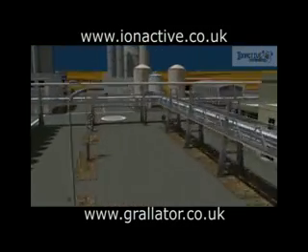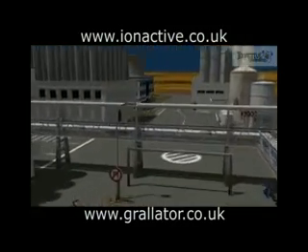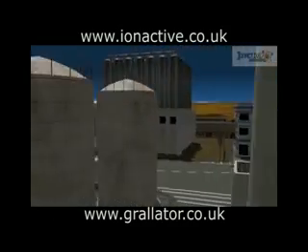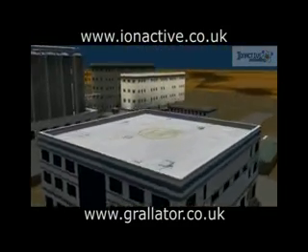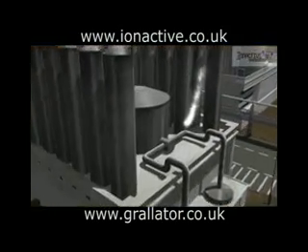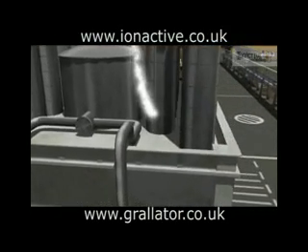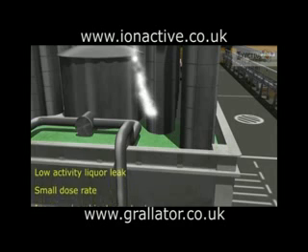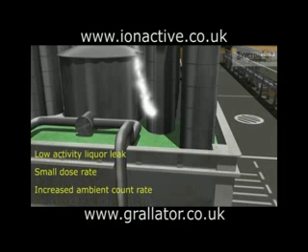For widespread contamination of an area by a radioactive material, the energy reaching the GM tube will be small, as the inverse square law of distance and transit absorption will remove all but a fraction of incident particles. However, the radiation from the contamination will be measurable as an increase in the background radiation count level, which can easily be expressed in terms of an increase in the number of counts per second.